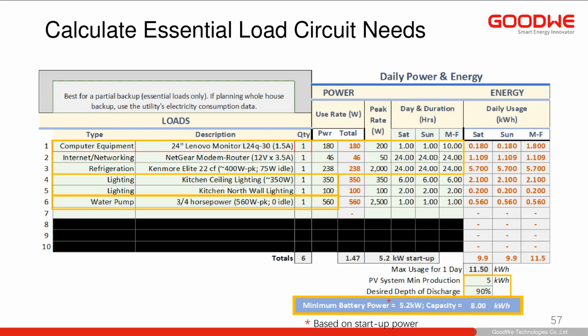Here I've listed out their average use and their peak use. That could be at the peak of their cycle or the inrush current. You want to know the potential draw that these devices have, particularly if you are not using an embedded ATS type ESS, where you don't have a quick transfer time and these loads could have to all restart. You want to know what the startup amperage or power, if you multiply it by the voltage, is. So in this calculation, it's telling me that Monday through Friday, over here on the right, is the type of day where I use the most energy, 11.5 kilowatt hours for these circuits.